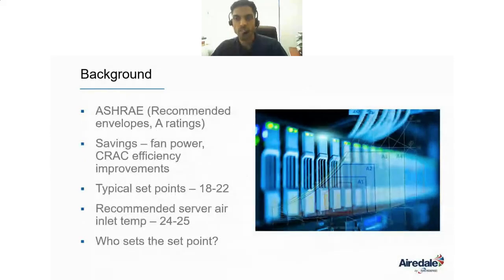The ASHRAE limits recommend a server inlet temperature up to 27 degrees Celsius, which obviously allows you to set a higher return air temperature. This converts to savings mainly in lower fan power, or in general, the efficiency of the CRAC units is higher with the higher return air temperature.